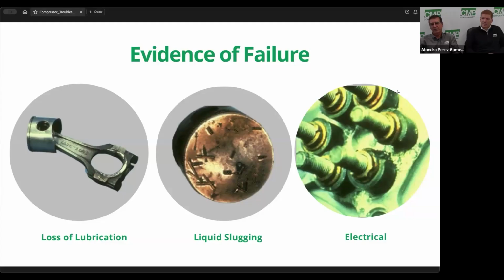Yeah, we have done oil analysis in the past, many years ago, and sent it out. I never have really recommended it to the customer because he just ain't going to do it anyway. But we have sent oil analysis off. You're looking for carbon in the oil, maybe a little moisture content, depending on how you seal it. A lot of times on a clear oil, they'll turn yellow. But the metal particles, aluminum, brass, you're looking for stuff like that in the oil.